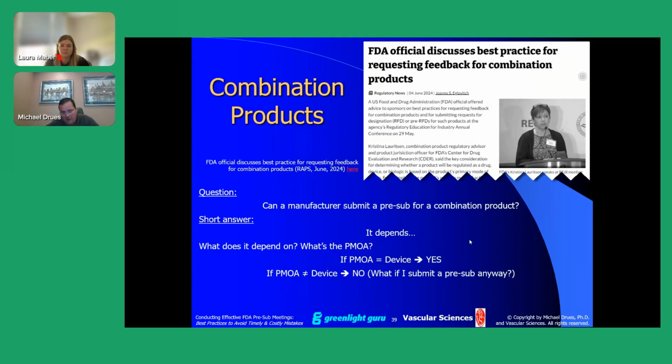For those of you that are not familiar with PMOA, listen to my combination products webinar that I did for Greenlight, I think a year or so ago. I go into this in a lot of detail. But suffice it to say, if the PMOA of your combination product is device, then yes, you can submit a pre-sub to CDRH. On the other hand, if your PMOA is not device, let's say it's a prefilled syringe or a transdermal patch or something, those are primarily drugs, not devices.